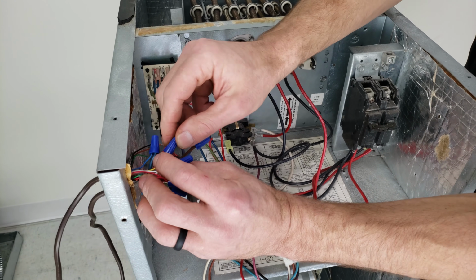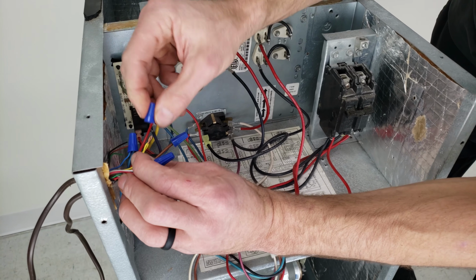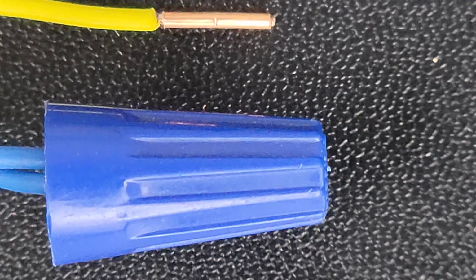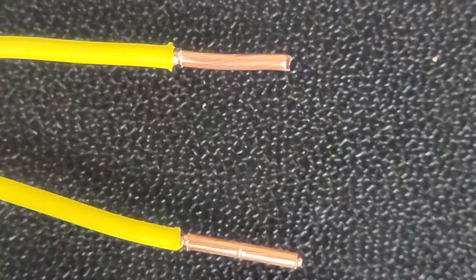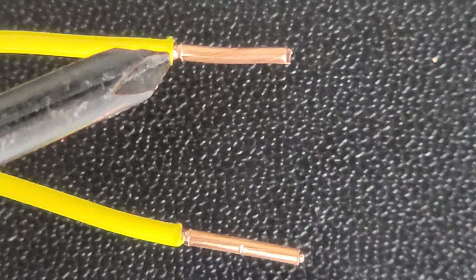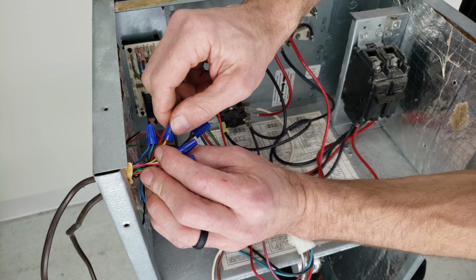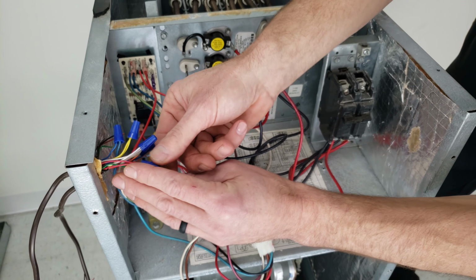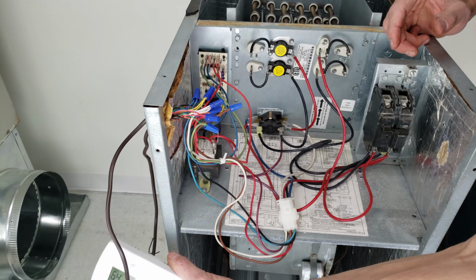So these wire nuts, making sure that they're tight. You could have had somebody cut into this and kind of scar the wire due to a bad wire stripping process, and you could have high electrical resistance right there.